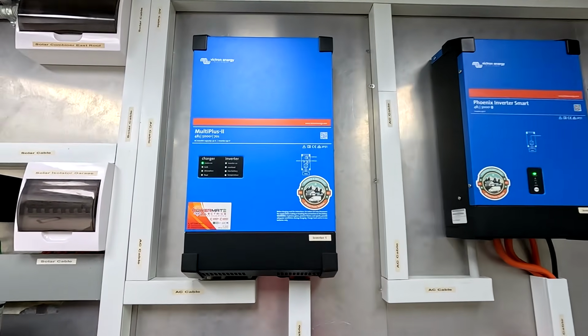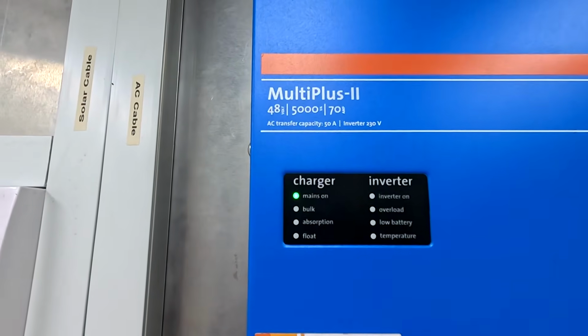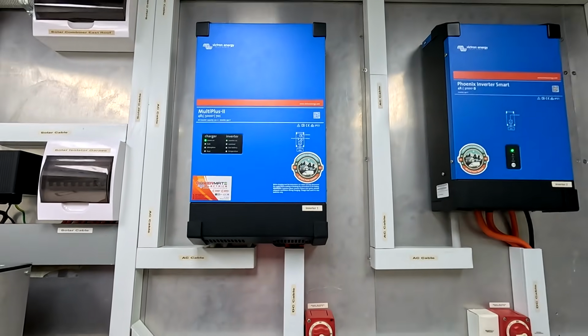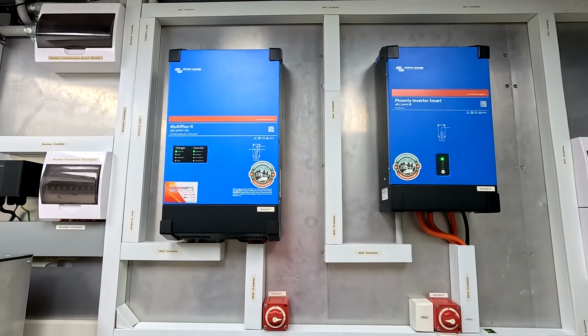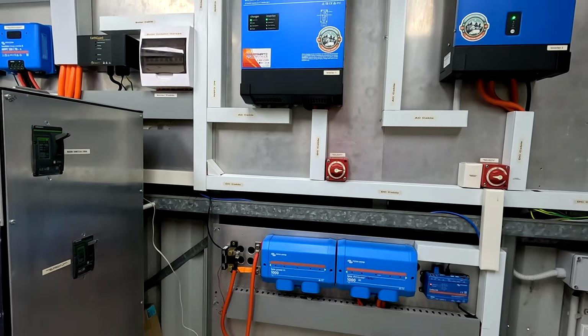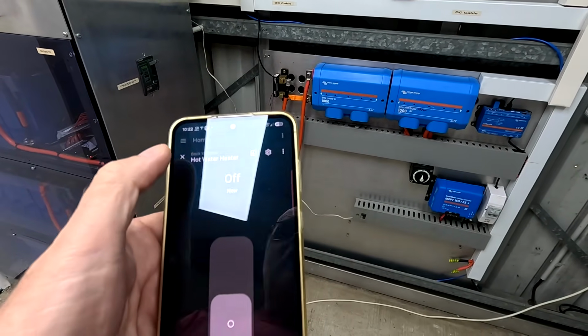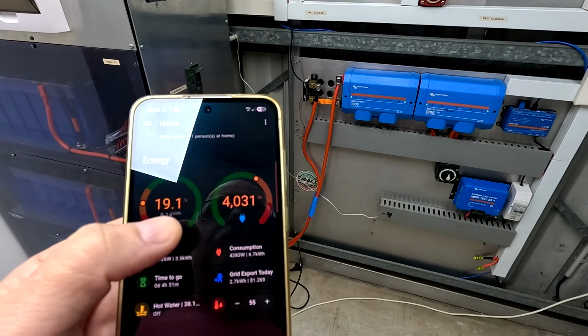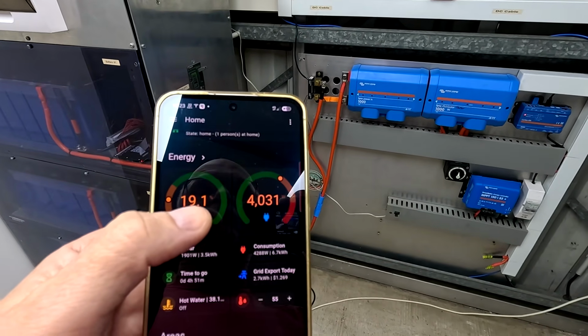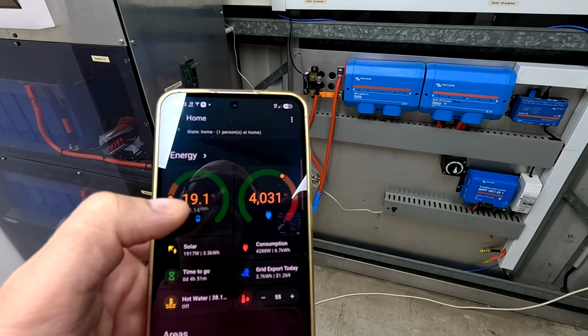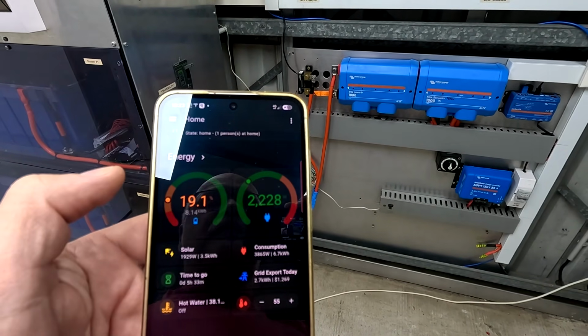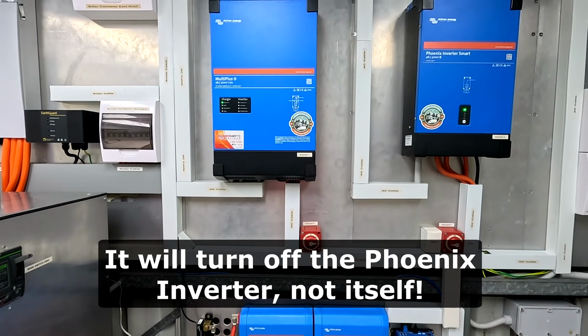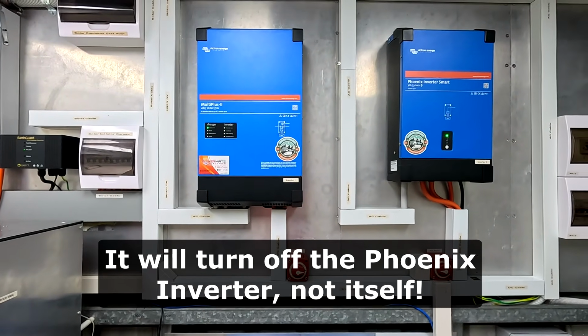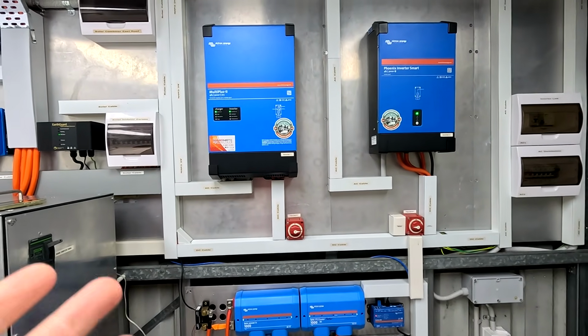There we go. And now the mains is on. And now we are running both systems at the same time, Phoenix inverter and multi-plus, to cope with this larger load. Alright, let's turn off the hot water again. And we should see the power usage dropping to around 2 kilowatts or so. Yep, 2.2 kilowatts. And the phoenix inverter will turn off if we go under 2 kilowatts for 1 minute. And the multi-plus will then again be the only inverter which produces power. So this all works pretty well as it did before.